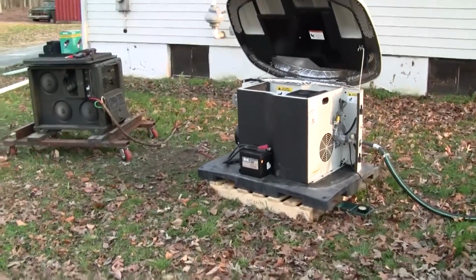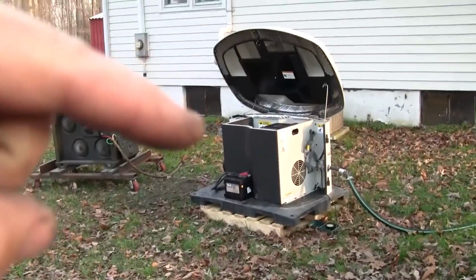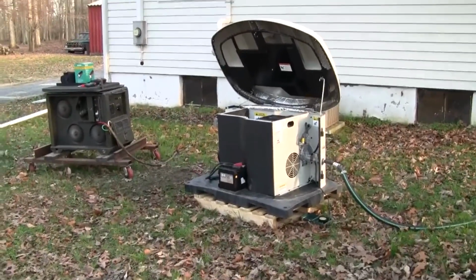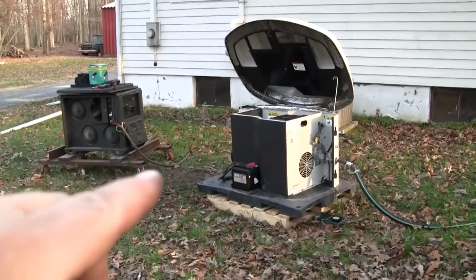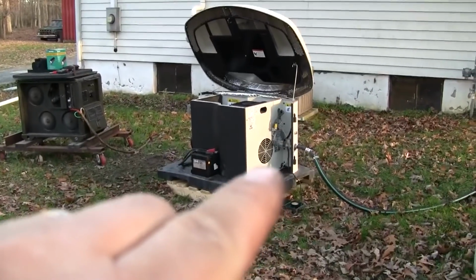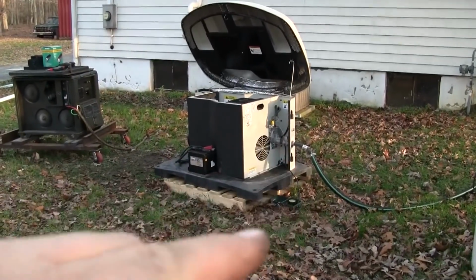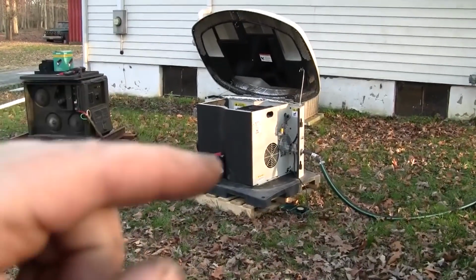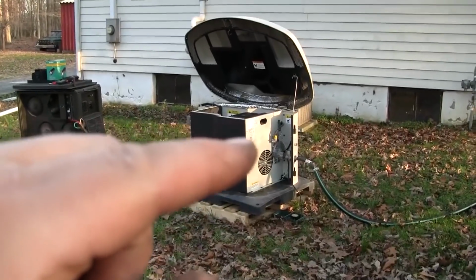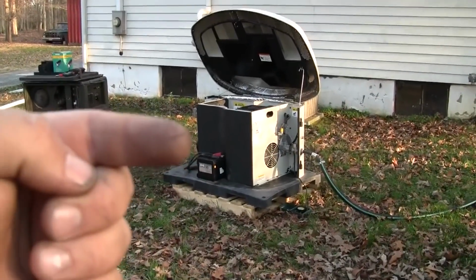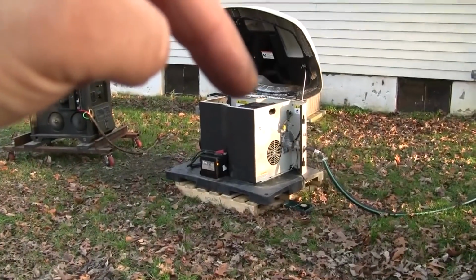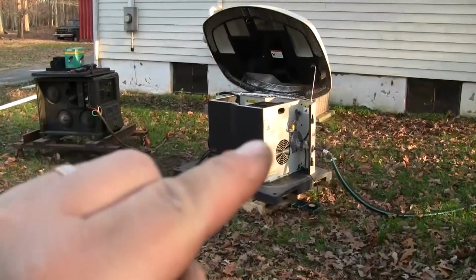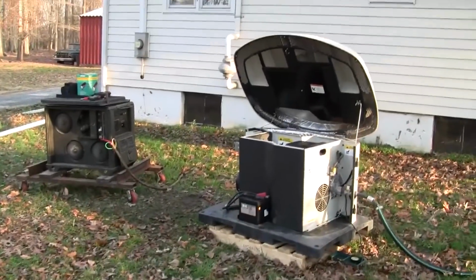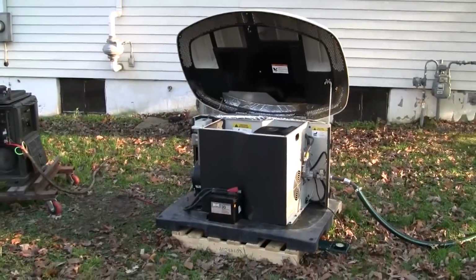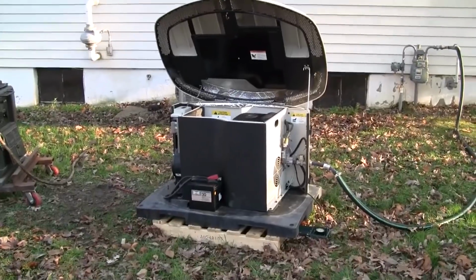As we approach higher and higher loads, I'm going to want to close the clamshell there. That is actually a part of the engine's cooling system, or the unit's cooling system, I should say. So the fresh air is being drawn in through that screen right there, the engine's flywheel, and also at the generator end. That cool air is being pushed over the engine, and the cool air from the rear is obviously going over the generator. They converge in the center and are pushed down past the muffler and then out the back, out of the rim of the lid. So right now, the only thing that's cooling the muffler is natural convection, the heat rising off of the muffler.